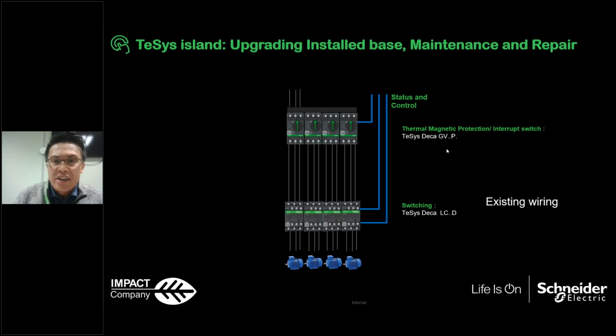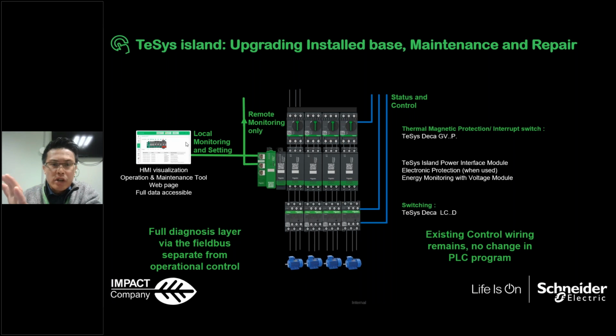So how can we upgrade the existing installed base, or for maintenance and repair, if we are now using conventional contactors? Imagine this is the conventional setup: in the existing panels you have circuit breakers for short circuit protection and contactors to drive the motors. You can then use the power interface module, which is a PCB board, that can monitor all the data from the motors without changing the contactors. With this power interface module you can have all the energy monitoring with the voltage module, and then you can achieve all the benefits and values we talked about before. So it is very simple: using the existing panels, you can upgrade them to achieve those values without changing the contactors and without changing the whole system.